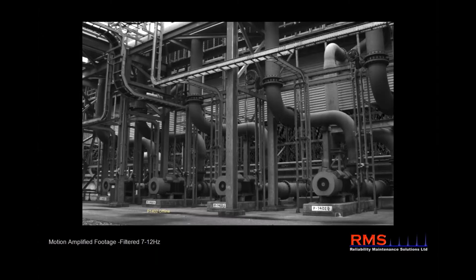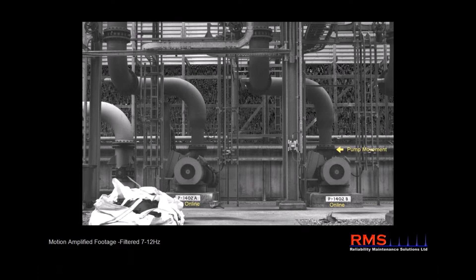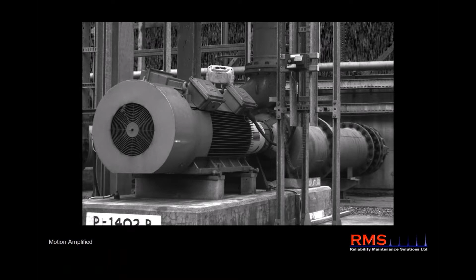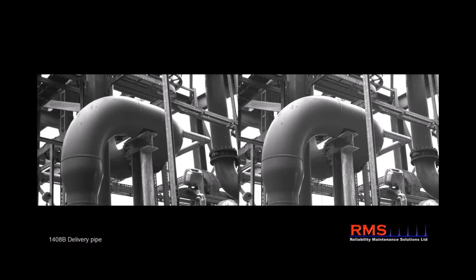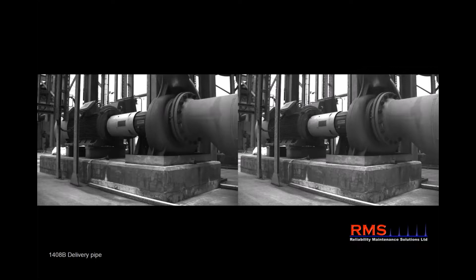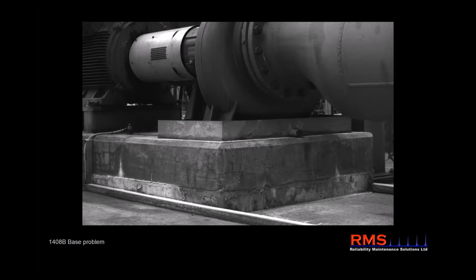Okay, let's talk about comprehensive scans. Again, this was a routine scan, but the idea of going through and scanning and measuring all your assets could be daunting with other tools. But going back to that full field vibration, where you get a comprehensive scan over this entire set of pumps, they were able to capture this again on a routine scan. Having that vast data collection, done at a pretty fast rate, allows you to go through and do scans, baselines, looking over your assets, and capturing this - which otherwise would be a challenge.